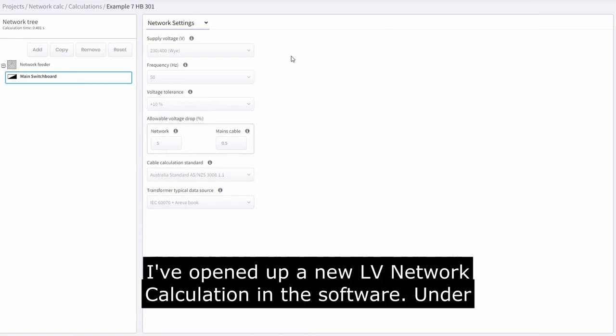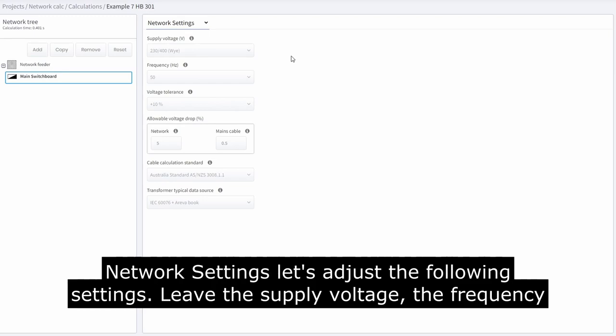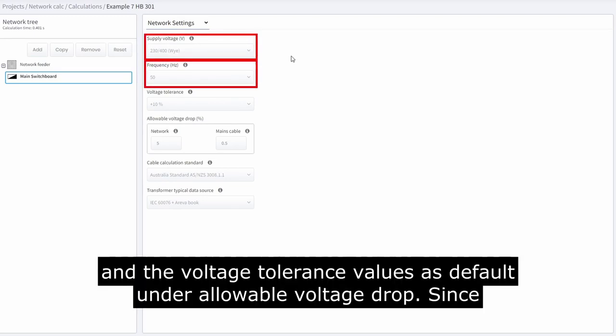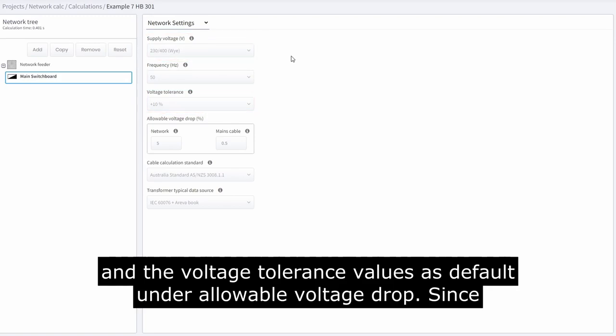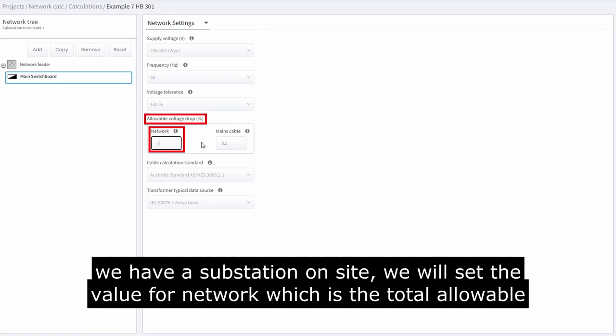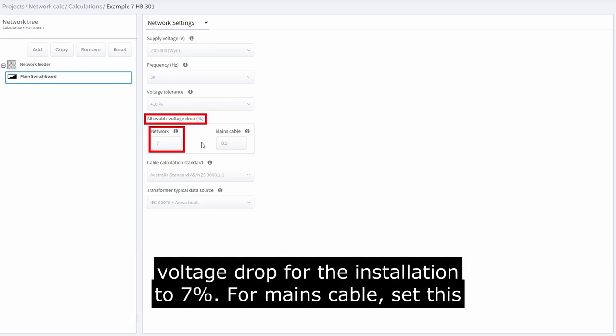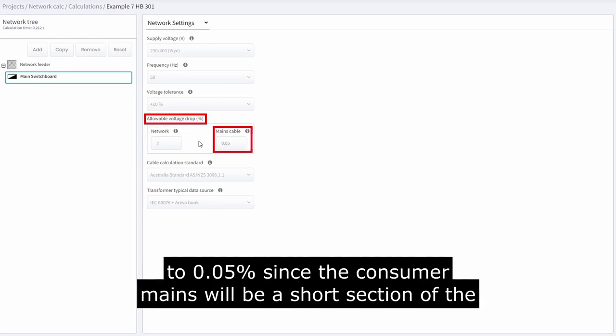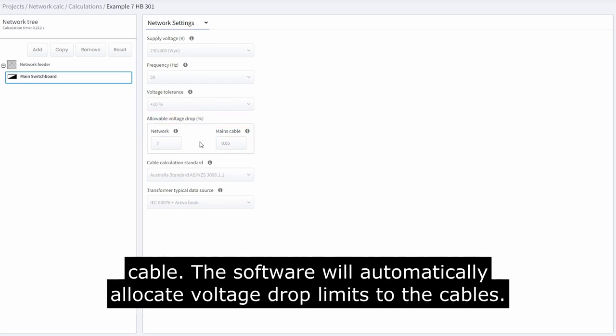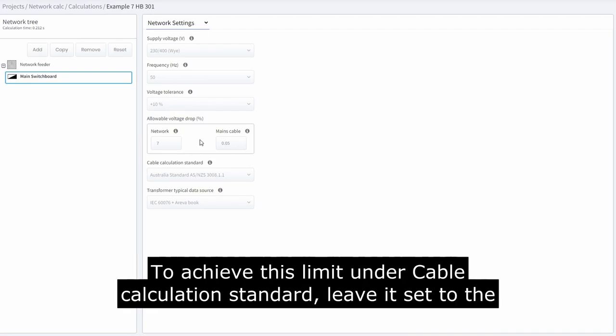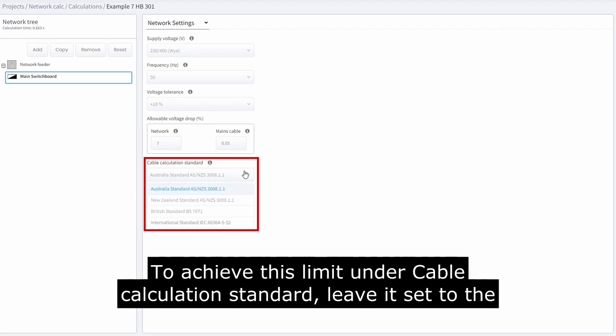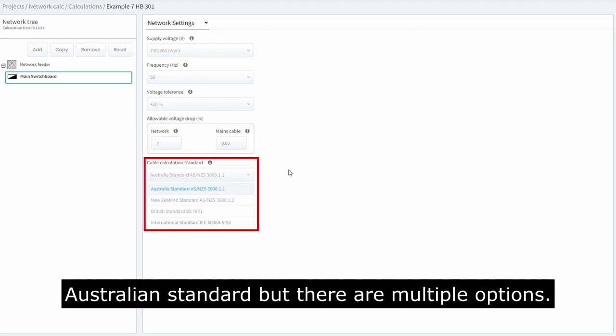I have opened up a new LV network calculation in the software. Under network settings, leave the supply voltage, frequency, and voltage tolerance values as default. Under allowable voltage drop, since we have a substation on site, set the value for network — which is the total allowable voltage drop for the installation — to 7%. For mains cable, set this to 0.05%, since the consumer's mains will be a short section of cable. The software will automatically allocate voltage drop limits to cables to achieve this limit. Under cable calculation standard, leave it set to the Australian standard, though there are multiple options.